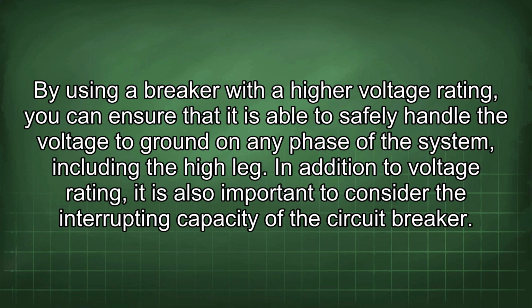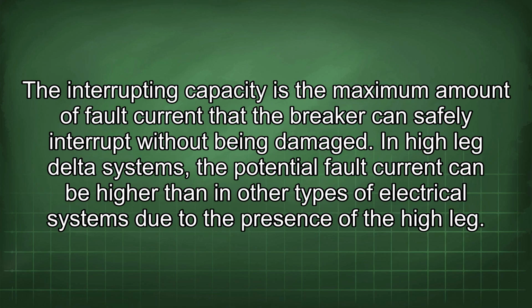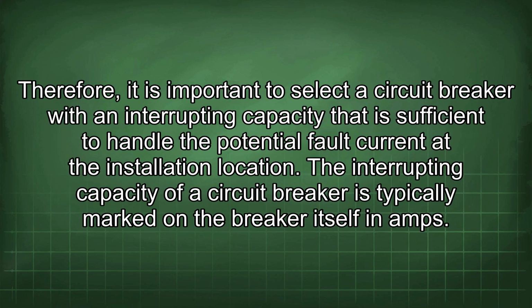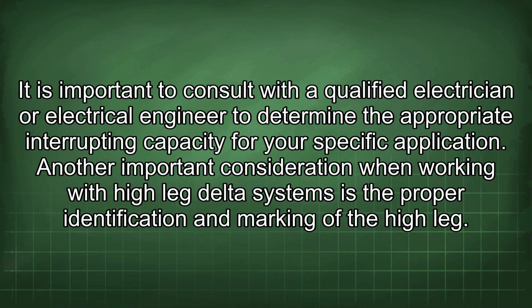In addition to voltage rating, it is also important to consider the interrupting capacity of the circuit breaker. The interrupting capacity is the maximum amount of fault current that the breaker can safely interrupt without being damaged. In high-leg delta systems, the potential fault current can be higher than in other types of electrical systems due to the presence of the high leg. Therefore, it is important to select a circuit breaker with an interrupting capacity that is sufficient to handle the potential fault current at the installation location. The interrupting capacity of a circuit breaker is typically marked on the breaker itself in amps.